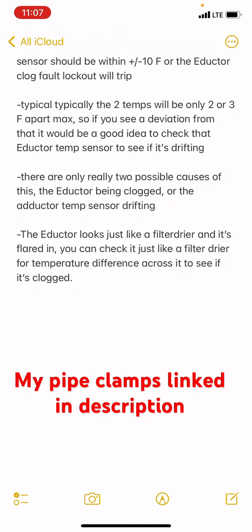They're going to be very close together. There are only really two possible causes of this fault code tripping: the Eductor itself actually being clogged, or the Eductor temp sensor drifting.